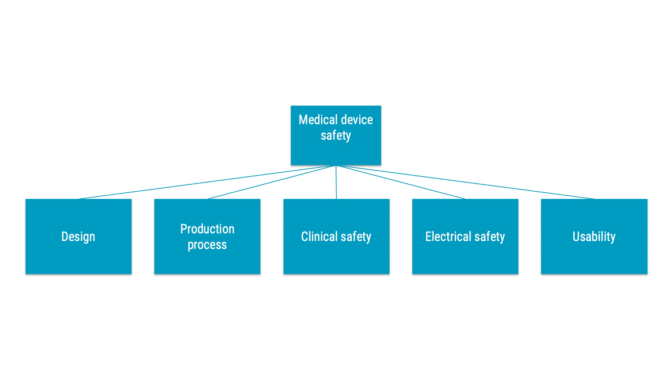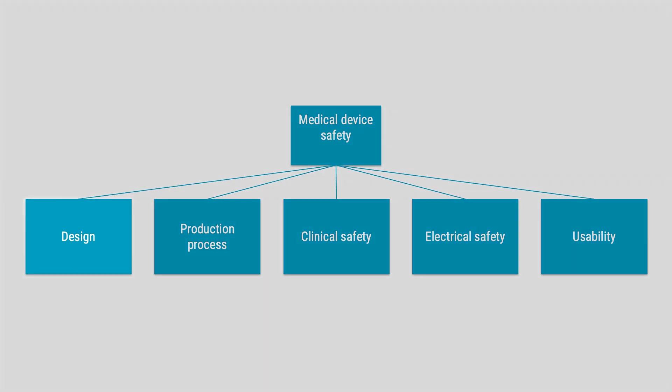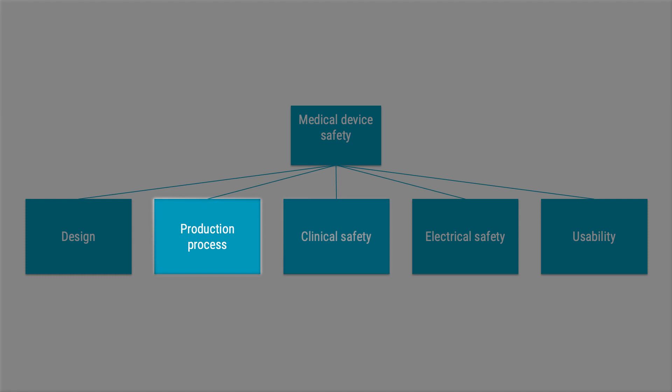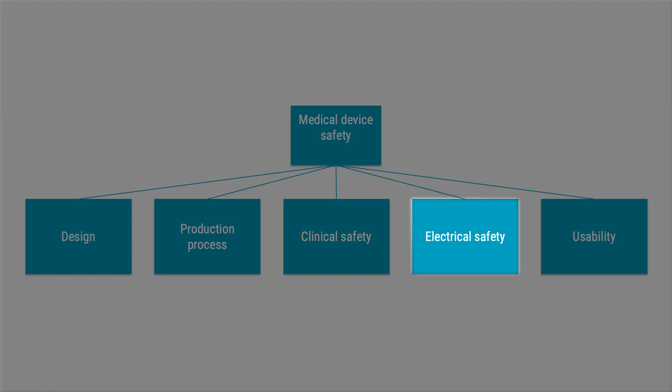Let's take one more look at the relationship between safety and risk management and safety and usability engineering. Medical device risk management, according to ISO 14971, is focused on the safety of the medical device in general. That overall safety is based on a lot of different areas — for example, risks from design flaws or failures in production, clinical safety including side effects or after effects, electrical safety, and of course the usability of the medical device.